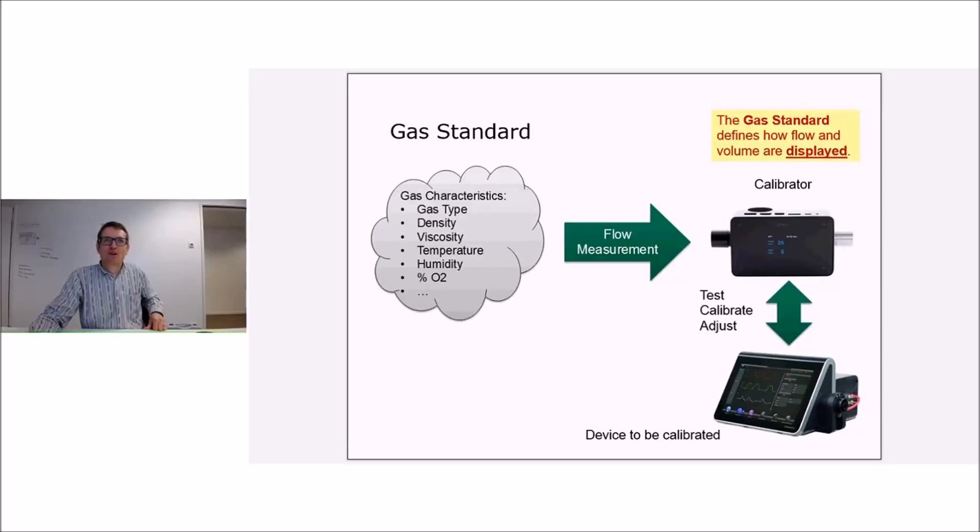So all these different properties—and what also comes, I mean, these devices, they're designed for air and oxygen. So if you measure another gas, for example nitric oxide or nitrogen or anything like that, you have to tell the PF300 that it is a different gas with different viscosity and all that kind of thing.